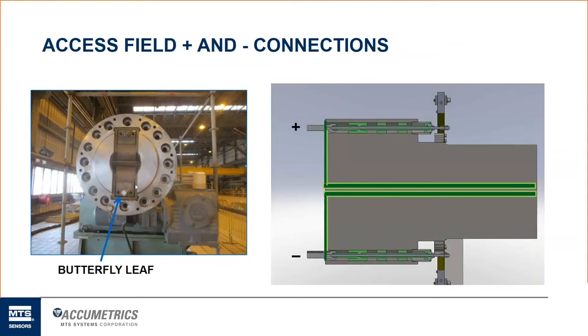So one of these copper bus bars will be the negative side and one will be the positive side. They're isolated from the rotor by typically G10 or G11 fiberglass material. And then as well from each other with another piece of insulation material. So this one on the right is a cross-sectional view of how we make that connection. So inside that coupling flange bore is how they bolt together the two butterfly leaves that match up.